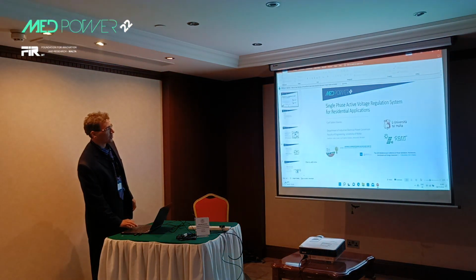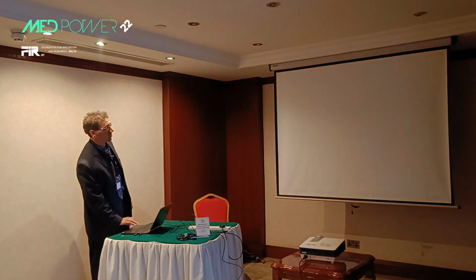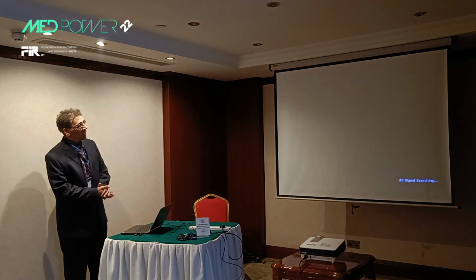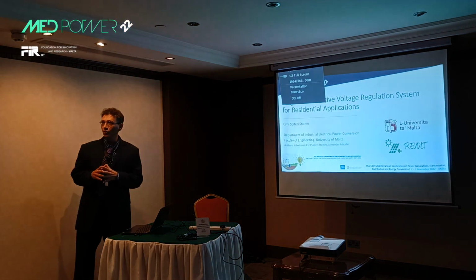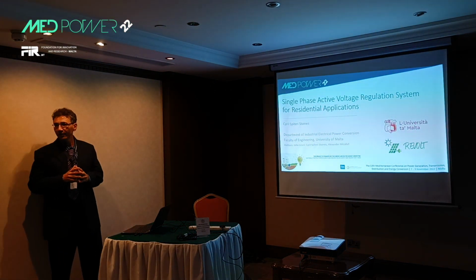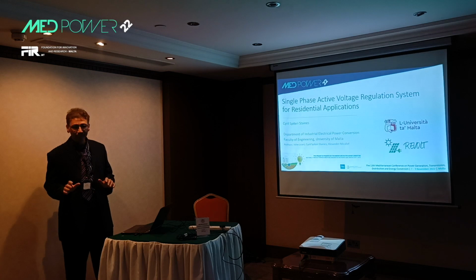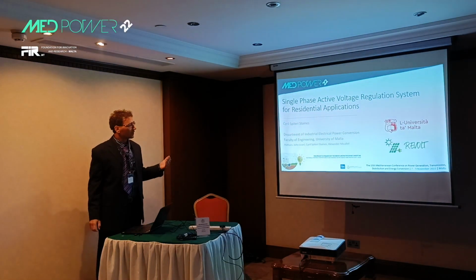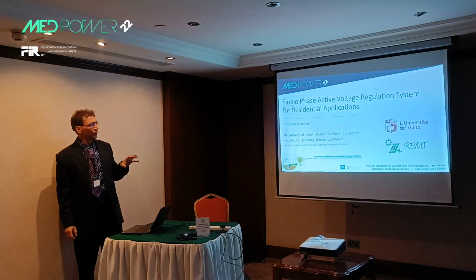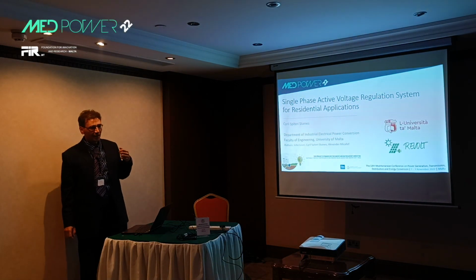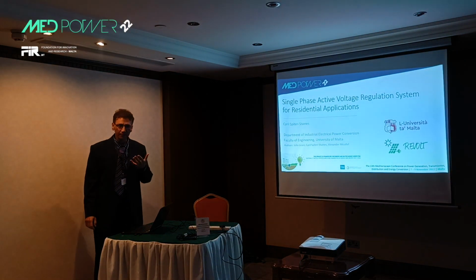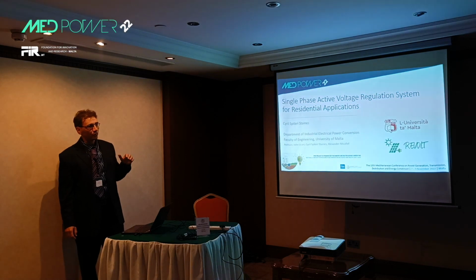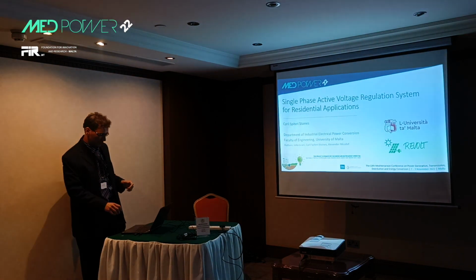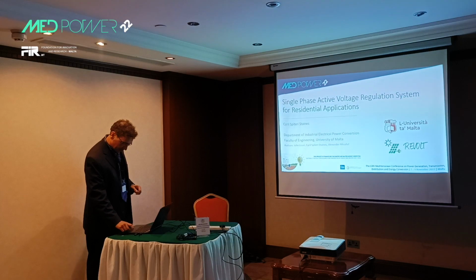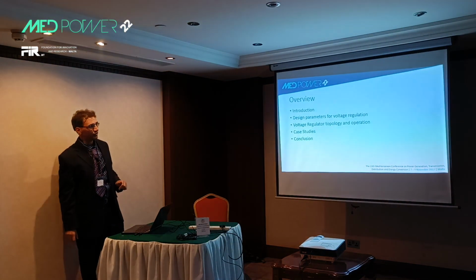So I ended up in a session with the majority of energy community people. So over here, I will be introducing a product which will allow energy communities to work whatever happens to the voltage of the grid. Okay? So this is a single-phase active voltage regulating system which will allow the voltage of the consumer to be kept at a constant value, so that it will be within the plus or minus 10% allowed by the grid regulations.